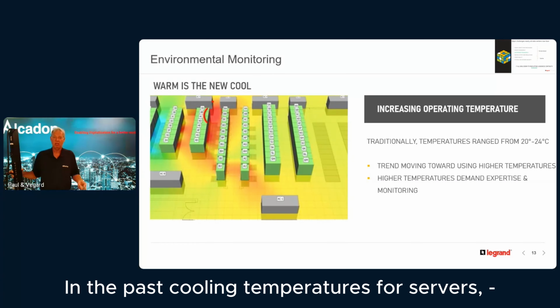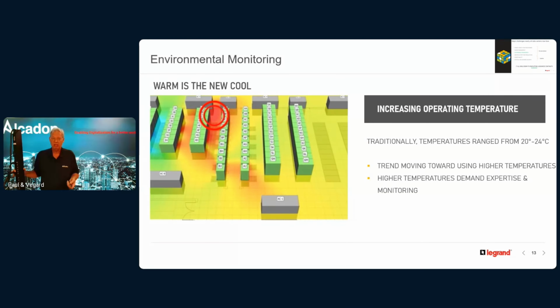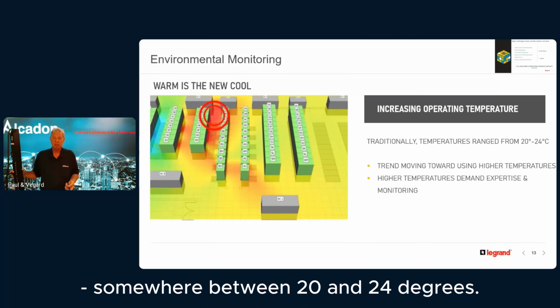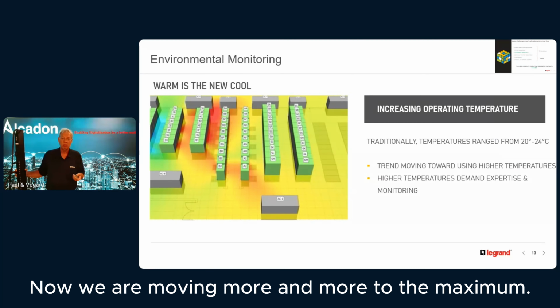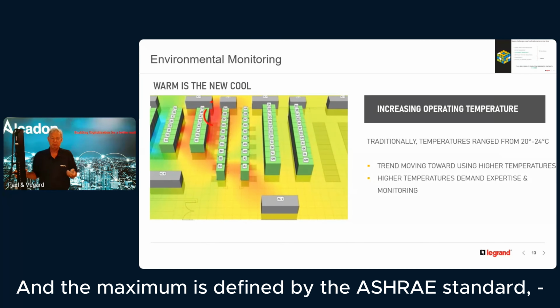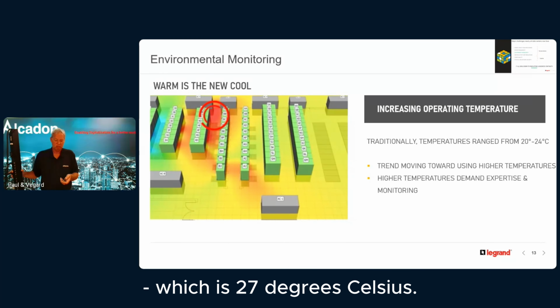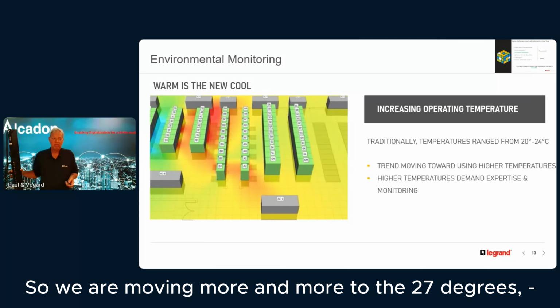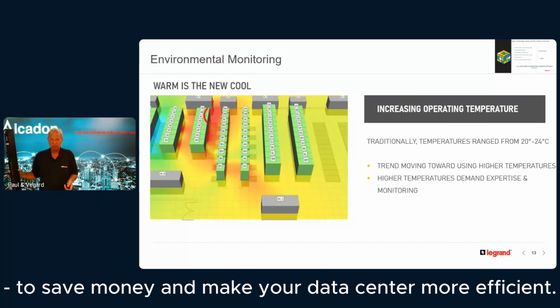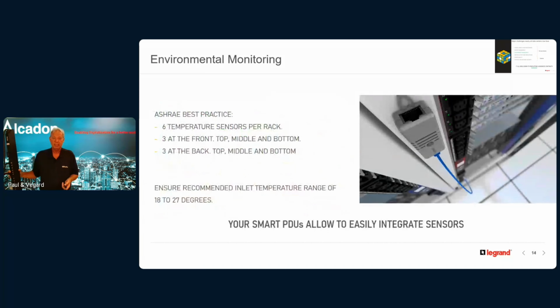In the past, cooling temperatures for servers, let's say the inlet temperatures, were somewhere between 20 and 24 degrees. Now we are moving more and more to the maximum, and the maximum is defined by the ASHRAE standard, which is 27 degrees Celsius. So we are moving more and more to this 27 degrees just to save money and make your data center more efficient.